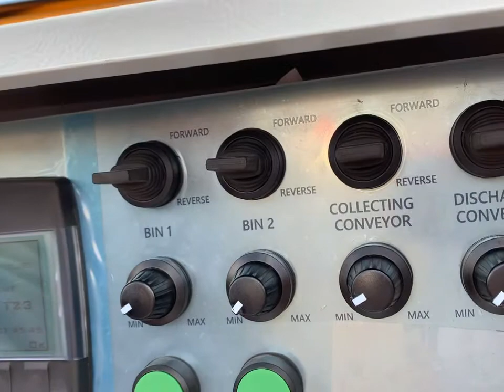You have to start at the end with the discharge conveyor, which has to be running before the pug mill can run. Then the pug mill has to be running before the collecting conveyor can run, and the same goes for bin 2 and bin 1. Everything has to be satisfied in order so that you can't overload the material.